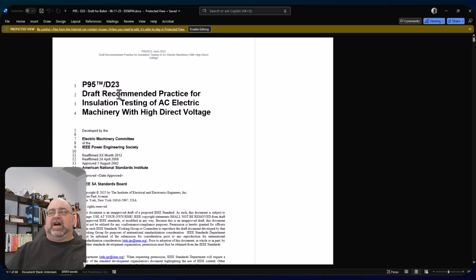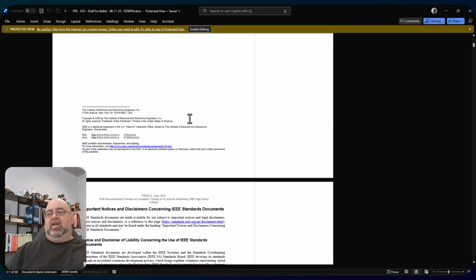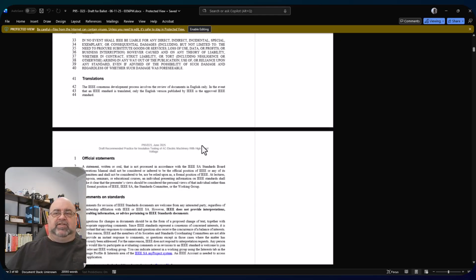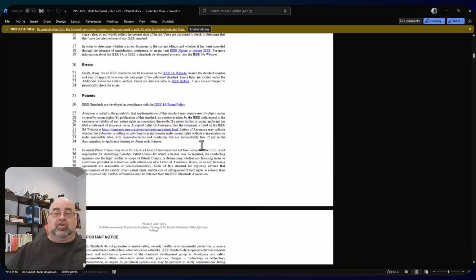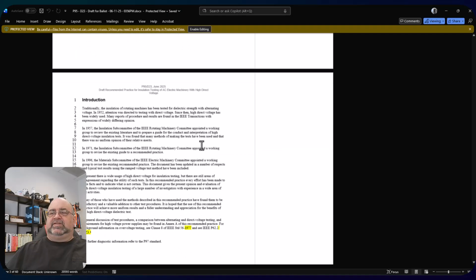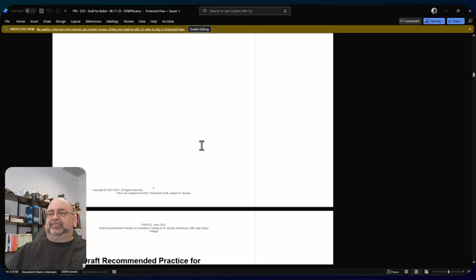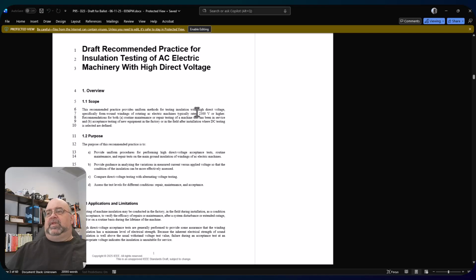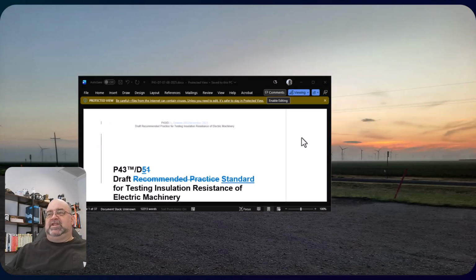Okay, so this is the one: draft recommended practice for AC electric machinery with high pot testing. This is where you apply high DC voltage to the stator and you measure leakage across to the frame. This is scoped for high direct voltage on motors 2300 volts or higher. So you notice it's not low voltage testing. Why is this important? Well, we're going to try to include some stuff in 1415, even though it's also meant for form coils, because there's no standard for this stuff for low voltage random wound machines. In IEEE, there's NEMA, but that's about it.